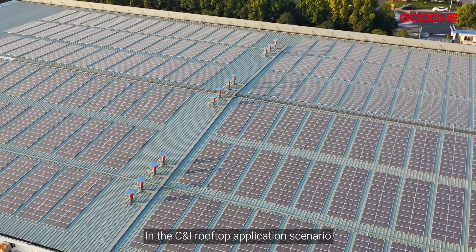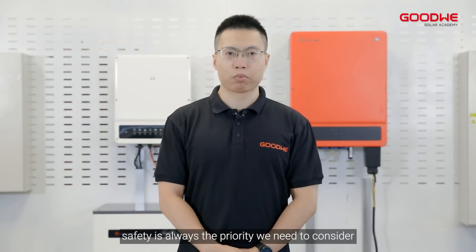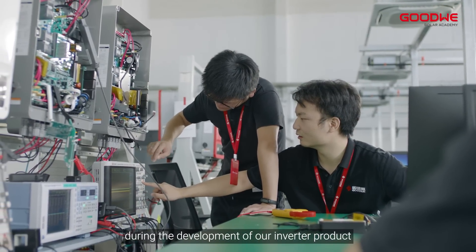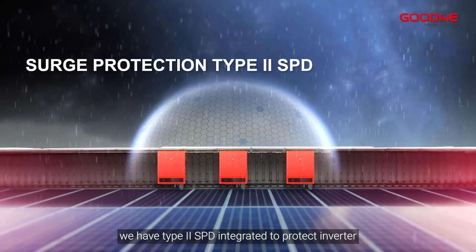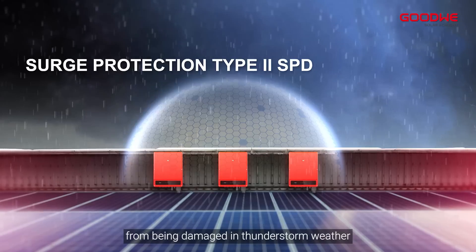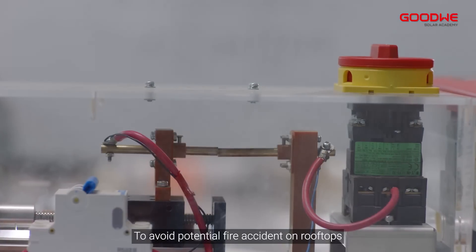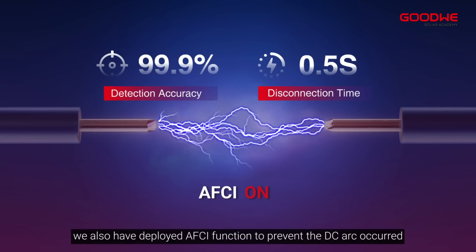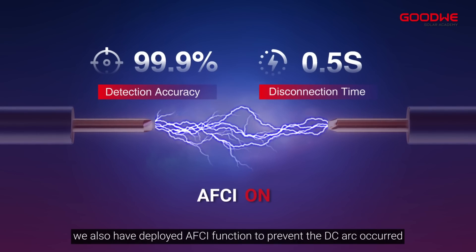In the C&I rooftop application scenario, safety is always the priority we need to consider during the development of our inverter product. For both DC and AC sides, we have Type 2 SPD integrated to protect the inverter from being damaged in thunderstorm weather. To avoid potential fire accidents on rooftops, we also have deployed AFCI function to prevent DC arc faults.